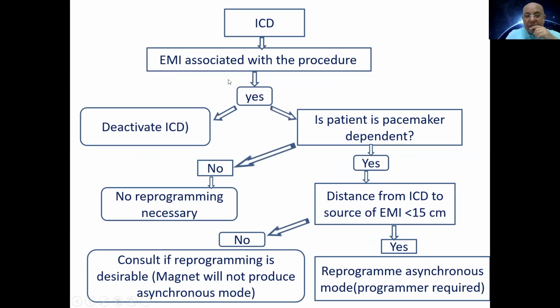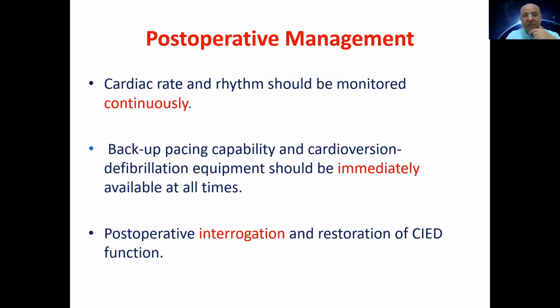If it is an ICD, you have to deactivate the ICD and check if the patient is pacemaker dependent. Not dependent, so no programming. Yes, dependent, look for the distance. If a small distance, you have to reprogram. If a long distance, you have to bring the consultant by any way to program. If you have an emergency situation, something else. Anyhow, post-operatively, you have to monitor the patient, be resuscitation ready, and call for interrogation.